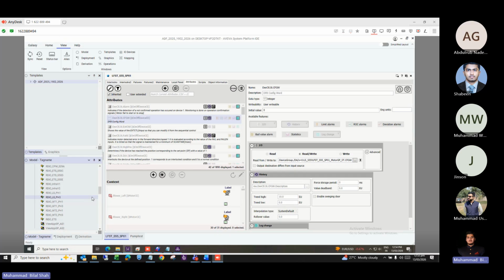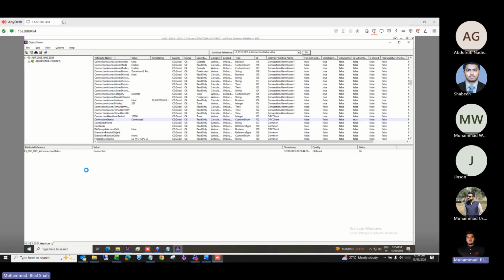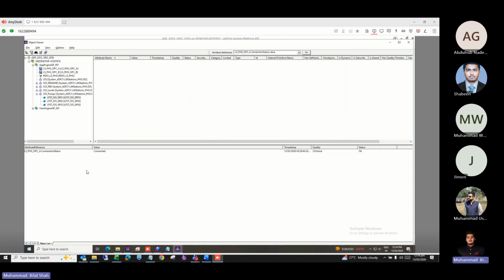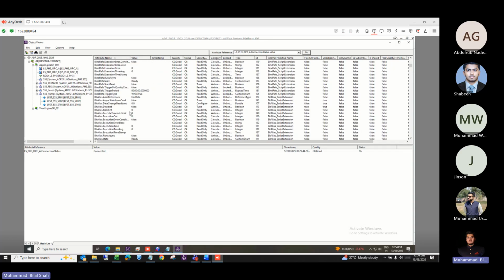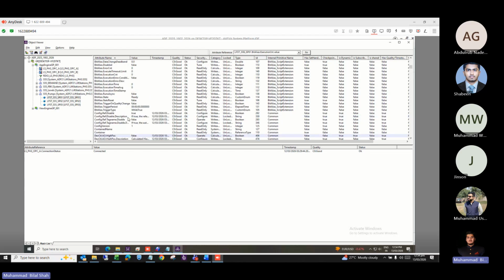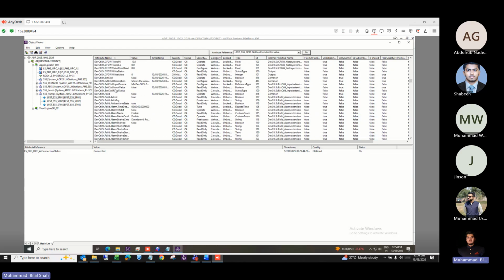If these two checks are fine, then you will go to your object, for example, in this case, pump, and you will check whether the quality is good or not. For example, this pump, and then you'll go into the object viewer of it, open it, and then you'll see the status of that particular attribute which you are trying to test. In this case, you will just figure out that attribute, for example this one we have over here, DIV CFGW.